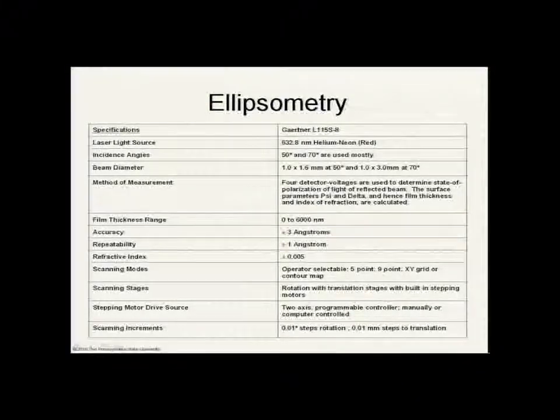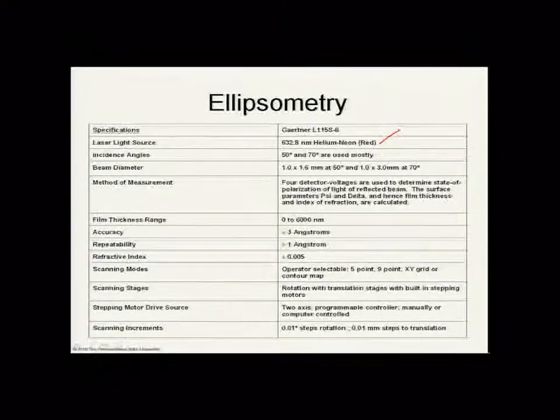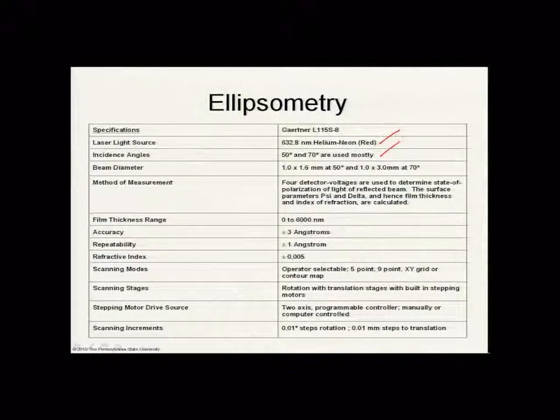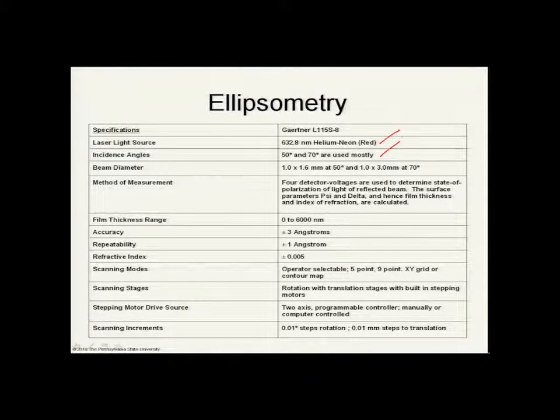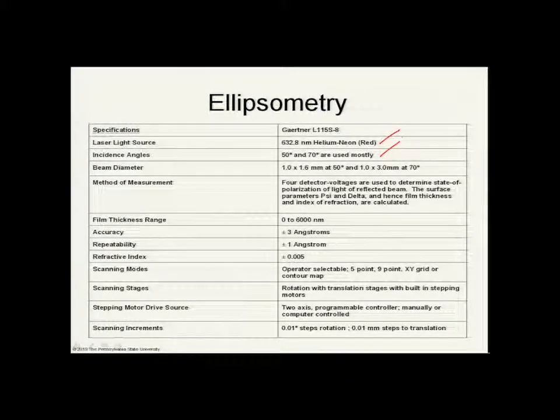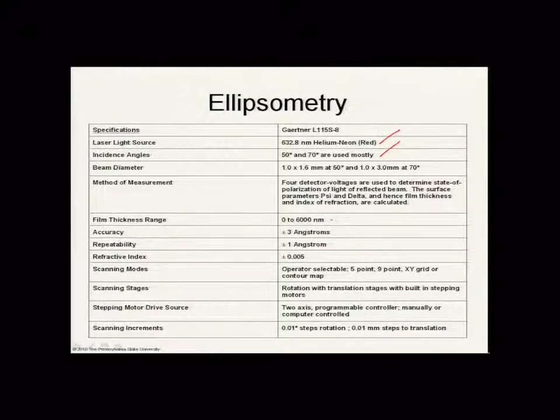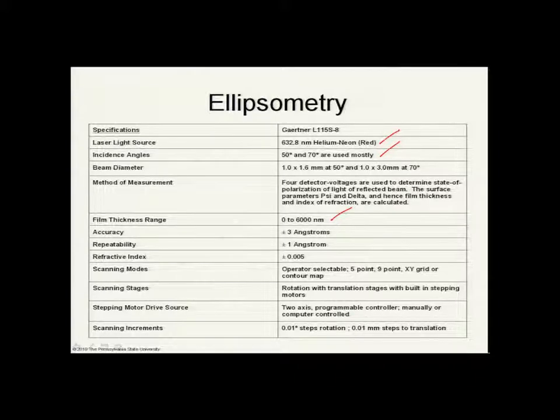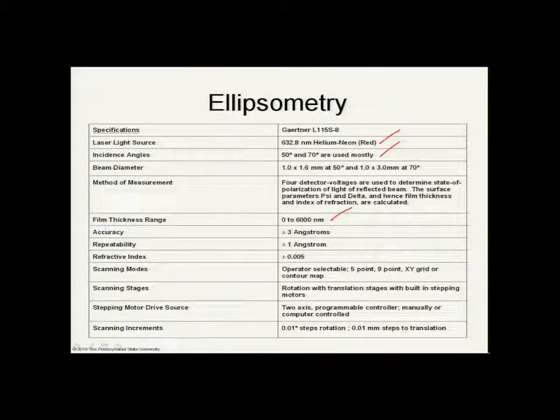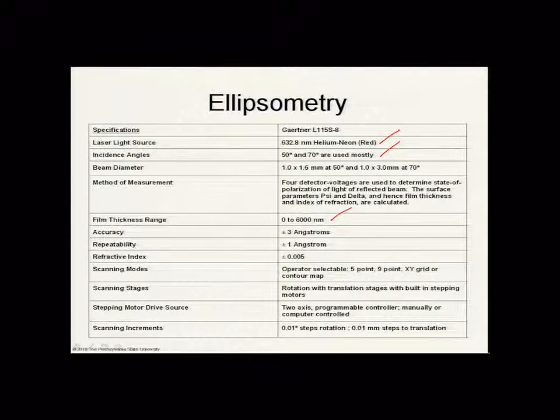For the particular ellipsometer in the clean room, we have a helium-neon red laser light source of a specific wavelength. We can change the incident and reflection angles; two commonly used angles are 50 degrees and 70 degrees for two-angle measurements. A notable characteristic is that it has a very broad operating range — it can measure very thin films up to relatively thick films in the micron range, with very high accuracy and repeatability.